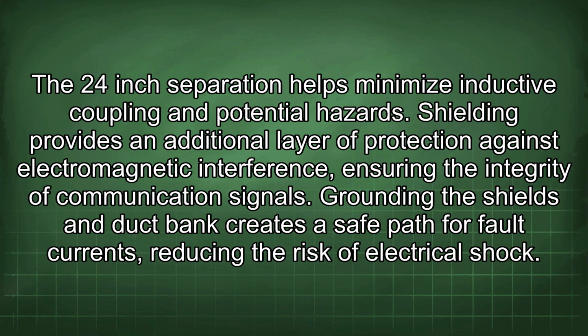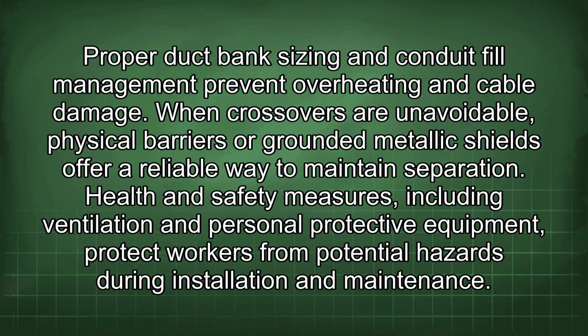Shielding provides an additional layer of protection against electromagnetic interference, ensuring the integrity of communication signals. Grounding the shields and duct bank creates a safe path for fault currents, reducing the risk of electrical shock. Proper duct bank sizing and conduit fill management prevent overheating and cable damage. When crossovers are unavoidable, physical barriers or grounded metallic shields offer a reliable way to maintain separation. Health and safety measures, including ventilation and personal protective equipment, protect workers from potential hazards during installation and maintenance.